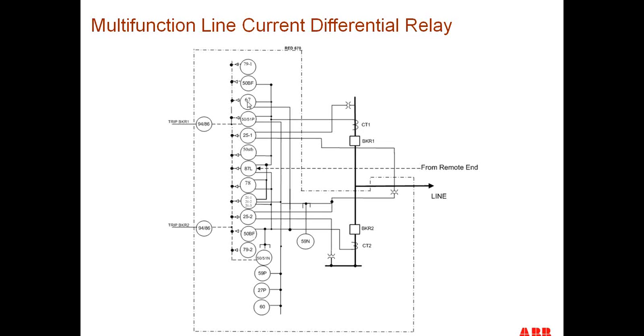And we also have a normal 87L relay and stub bus protection built into the scheme also. So these are the complement of relays that we would have for the line current differential relay. And also you see here three zones of distance protection that's there in case we have loss. We can either invoke it on loss of channel or have it running in parallel with the line current differential scheme.